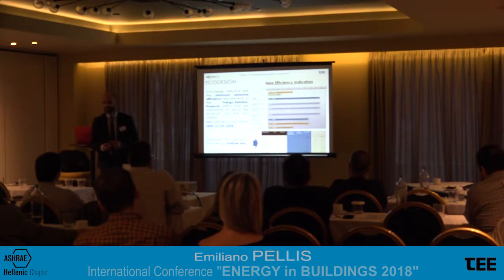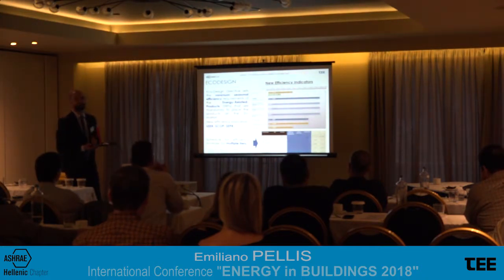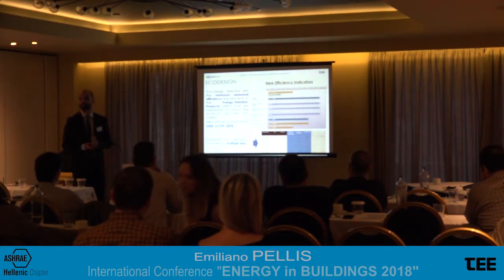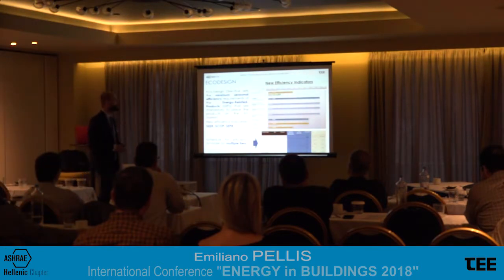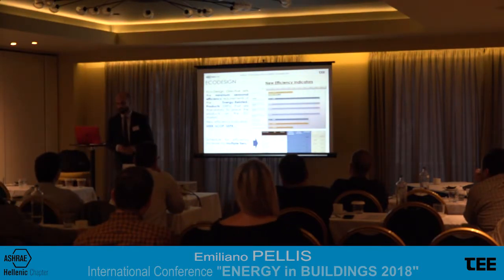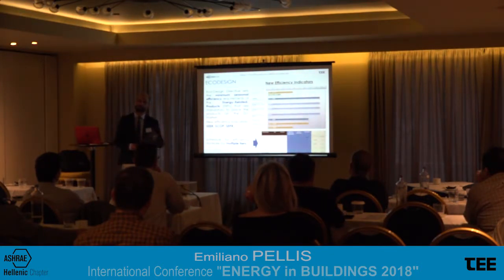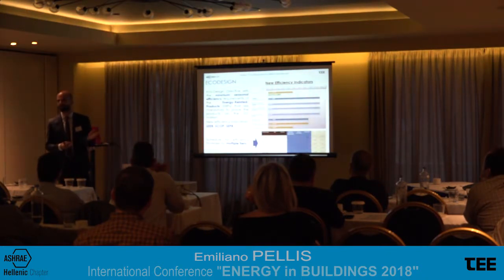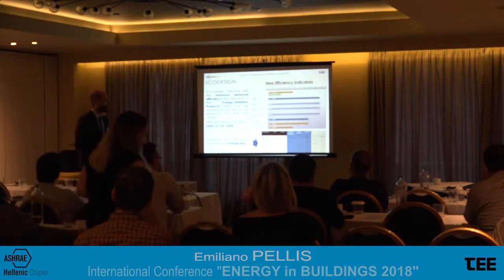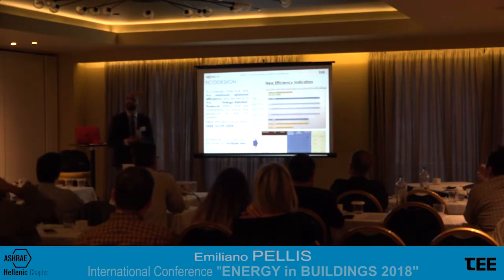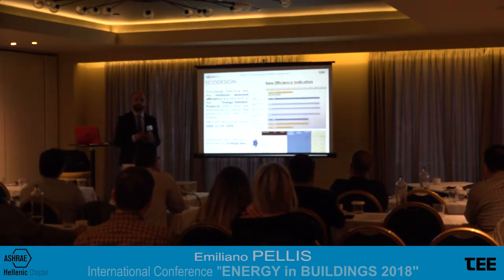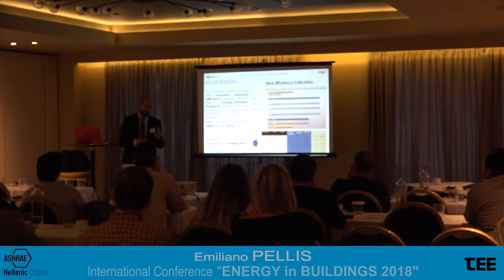eco-design. Eco-design is a very wide directive that sets the minimum efficiency requirements for energy-related products, including HVAC systems and in particular chillers. First of all, this is very important news for the European market, differently from the US, because in the past in Europe every manufacturer could produce a unit with whatever efficiency and place it on the market. No issue. Now it's different. There is a minimum efficiency to comply with before placing a product on the market. And very important, the minimum efficiency is related not to the full load, but to the seasonal efficiency, as we know that most of the operating hours of the unit will be spent at part loads.